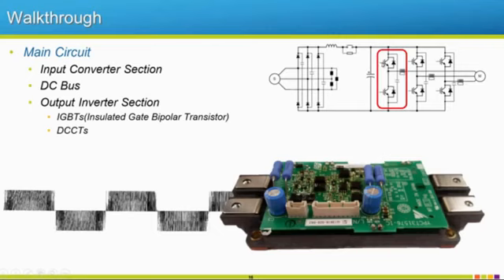IGBTs are similar to like MOSFETs except a MOSFET's really for low voltage, really high switching frequencies. IGBT is for higher voltages and a little bit lower, or quite a bit lower switching frequencies. Still fast, not anything like the old days, but they're getting faster and faster too. So look for newer drives being able to run higher switching frequencies.